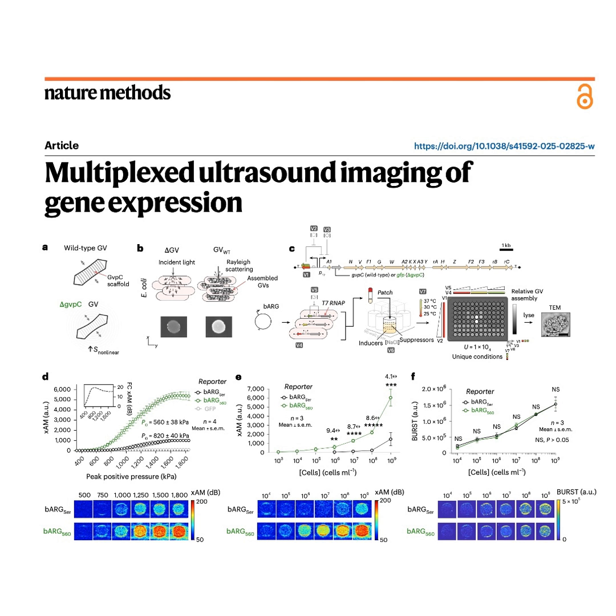So how do you fix that? They proposed a really elegant solution, a depth-corrected multiplexing matrix, or M2D. Instead of one master key for the whole image, you'd have a different key for every depth. So you'd tell the algorithm, for pixels at 1 centimeter deep, use this pressure calibration. For pixels at 3 centimeters, use this other one. That's the idea. It's like constantly refocusing a camera lens depending on how far away the object is.